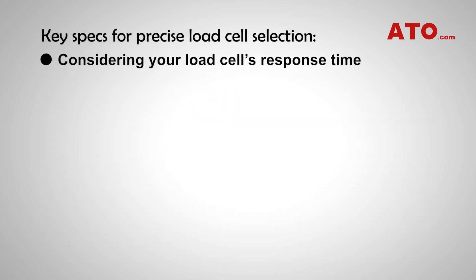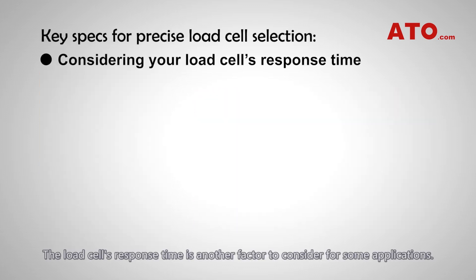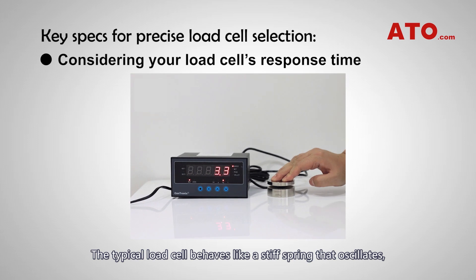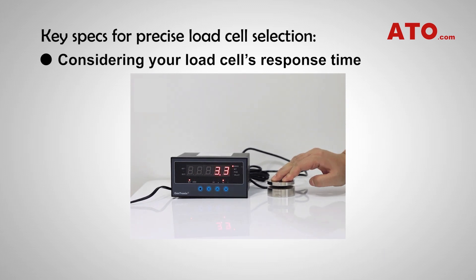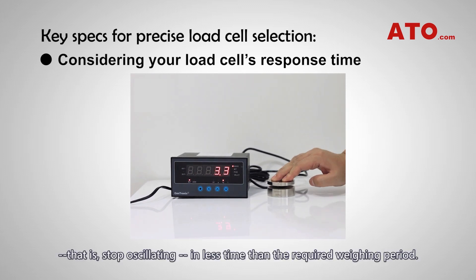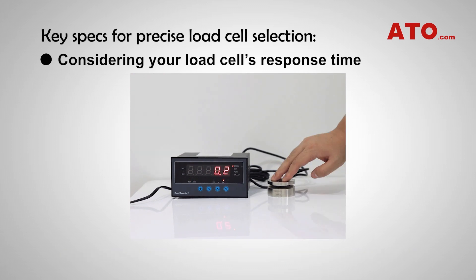Considering your load cell's response time. The load cell's response time is another factor to consider for some applications. The typical load cell behaves like a stiff spring that oscillates. So, to achieve an accurate weight reading, the load cell must settle — that is, stop oscillating — in less time than the required weighing period.